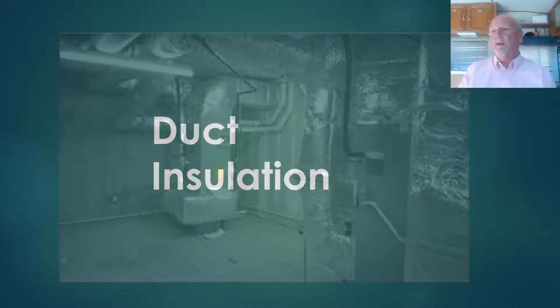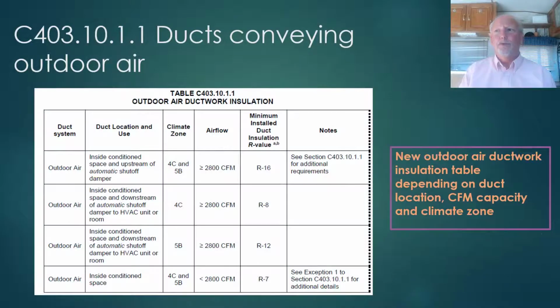So the last section we're going to cover here are some updates to the duct insulation requirements. I'm really glad that these tables were added to the code and that the previous outdoor air ductwork requirements were amended, because they were in a narrative format and were hard to figure out. So we've got several new tables to clarify the requirements for ductwork insulation.